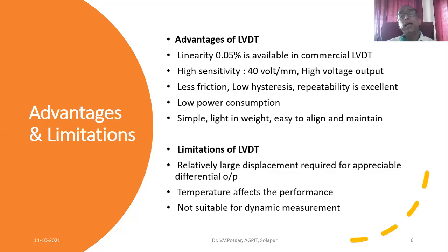It provides linearity of 0.05%. In commercial LVDTs, this linearity of 0.05% is available. Does this mean linearity is 0.05%? No, it corresponds to non-linearity of 0.05%. The relationship between input and output parameter is non-linear to the tune of 0.05%. So very small non-linearity - for the rest of the range, I have very good linearity, very good proportionality, which is essential in commercial LVDTs.